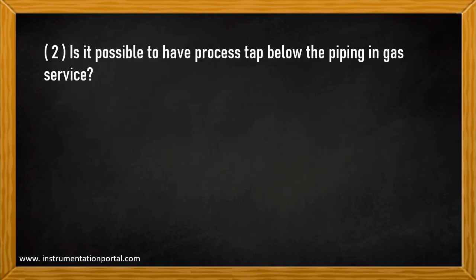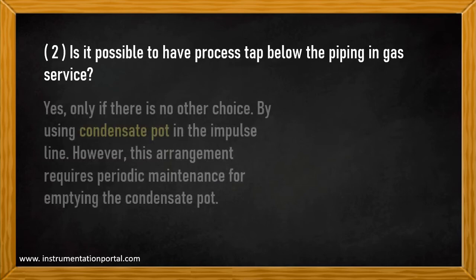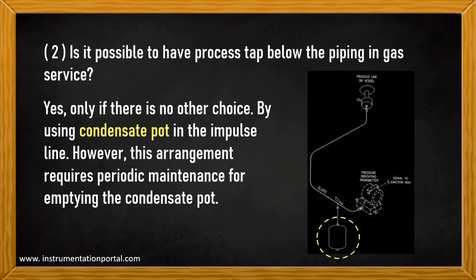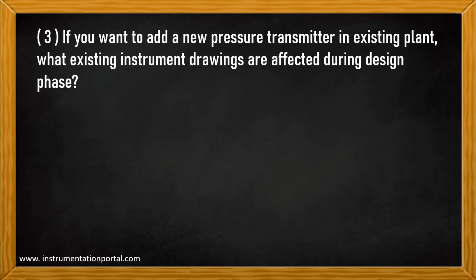Question number two: is it possible to have a process tap below the piping in gas service? Yes, only if there is no other choice. It can be achieved by using a condensate pot in the impulse line; however, this arrangement requires periodic maintenance for emptying the condensate pot. As shown in the drawing, there is a condensate pot to trap the condensed gas liquid component. Maintenance personnel must routinely empty this container.